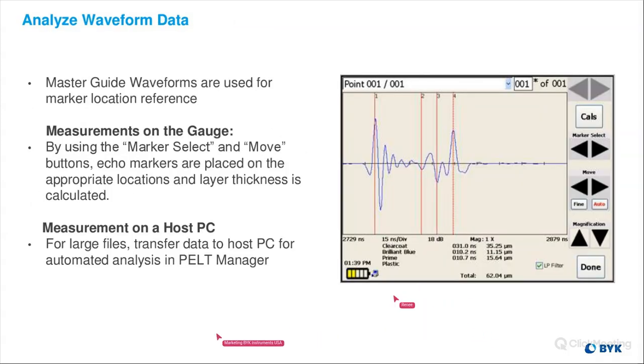So if I'm going to take measurements using this PELT gauge, I can go out and take one measurement, then mark it right on the display and get my information right away. I can see the thickness of each layer, and I can also see a total. This is great for spot checks. You can take it anywhere in your plant to take these measurements.